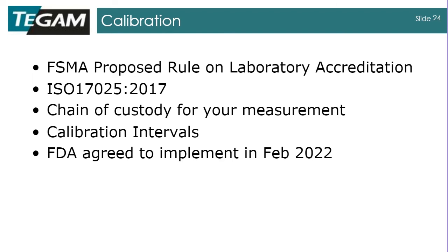Within that piece, they're recommending an international standard, ISO 17025 from 2017, and it is a description of how you manage your calibration laboratory and trace the measurements that you make. You can think of it as like a chain of custody for measurements. So when you make a measurement, that instrument was compared to some calibration instrument at a laboratory at some point, which was then compared to some laboratory standard to make sure that that measurement is good. And that's traced all the way actually to a national standard, in our case, NIST. So there's documentation that shows when your instrument makes a measurement, there's a paper trail all the way to a national standard level. And ISO 17025 describes that process of how you manage your lab to do that.